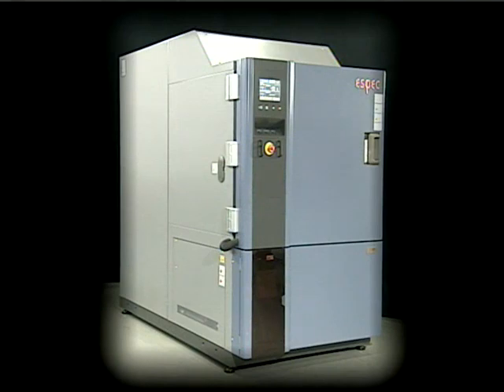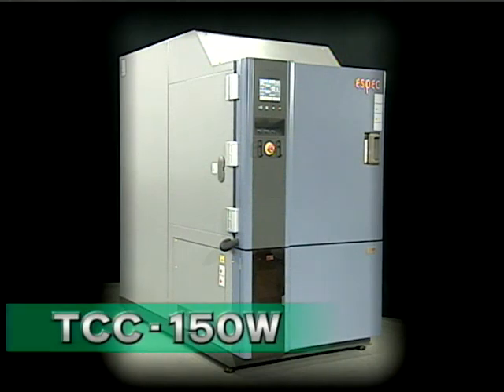What is the key technology of the TCC150W? Put simply, this test chamber has a mechanism that heats the specimens by heating the air in the chamber. A test chamber is required to provide the optimal balance between airflow and heating and cooling capacity. I believe that demand for this product will rapidly grow. This product has earned an excellent reputation because it offers features not available in conventional test chambers. Try the TCC150W for yourself to confirm its impressive performance.